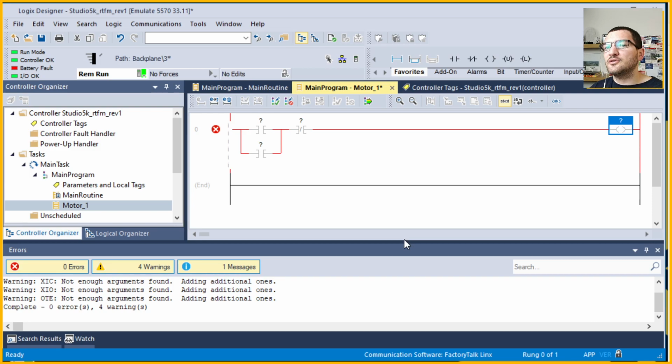Brilliant. So I showed you guys three ways you can add new ladder logic. So let's start addressing them. The first thing we've done is addressing them, and this is called a rung. So you've got your routine, and now we've got instructions, which is obviously just the mnemonics. A program consists basically of a set of input and output instructions. Input instructions are evaluated by the controller as being true or false when the controller carries out its scan. The controller sets the output instructions to true or false in response. So this is what an instruction does.